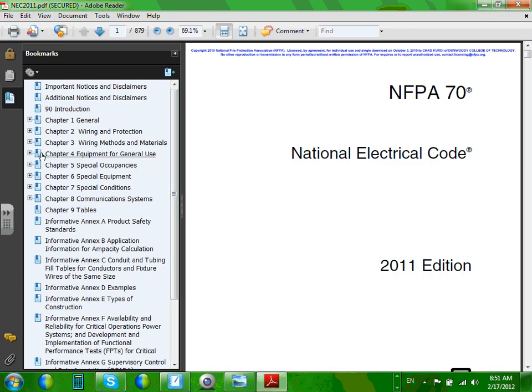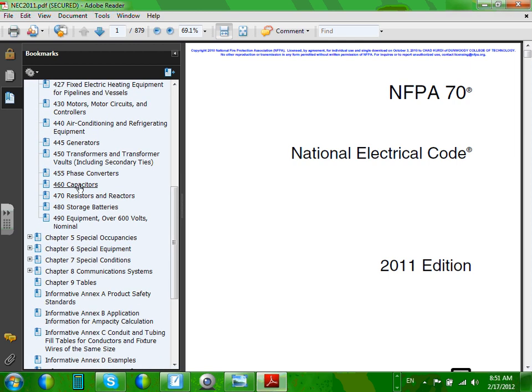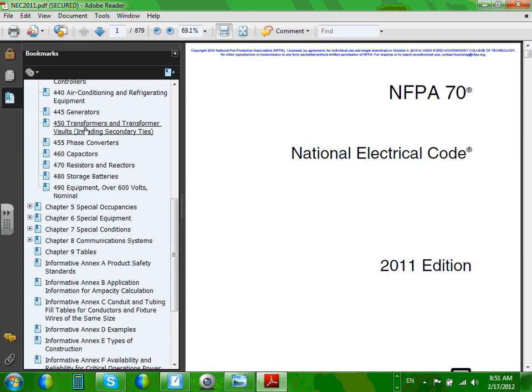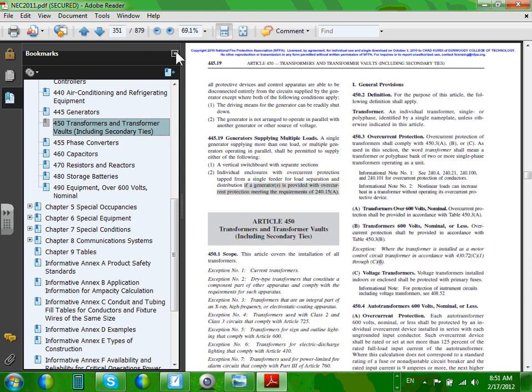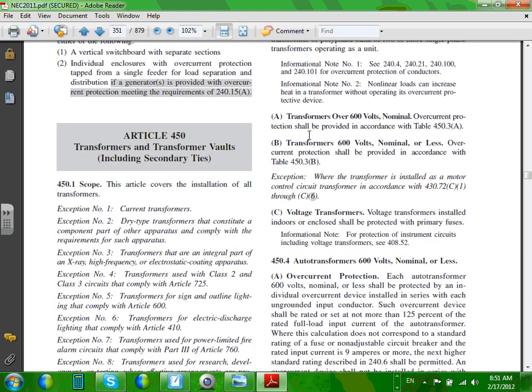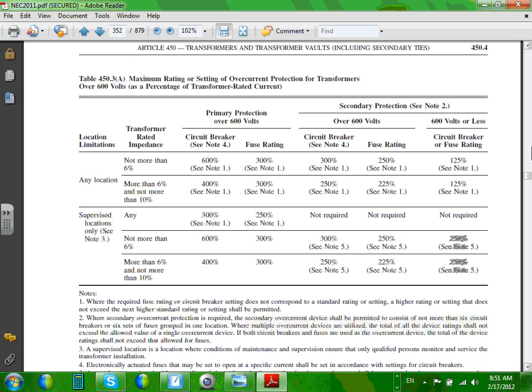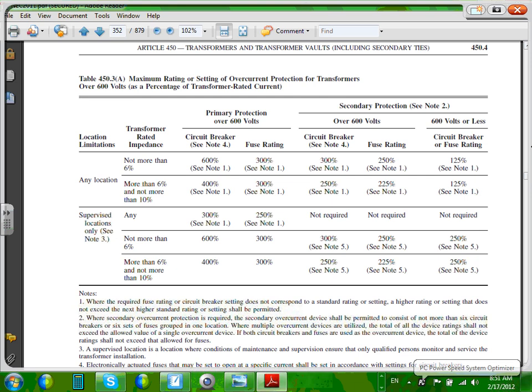I know when we used it, guys, we used it under these circumstances, which is right here. Transformers. And when you see it, probably you recognize it. This one. You guys remember that? 450.3A. We said it starts with transformers. If a primary or the secondary is over 600 volt, so we start with the primary, secondary over or under 600 volt, and you do the whole calculation. And if you guys, I don't know if you remember, I told you, if you don't know anything, any location, you default to any location.